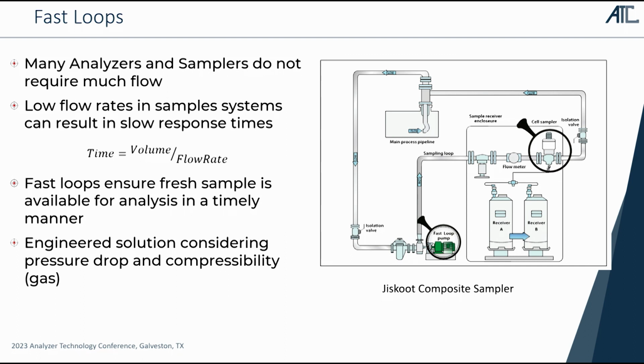Fast loops will help to ensure that we get a fresh sample over to where we're going to do our measurement, and they often have to be engineered properly. If it's liquids, we often have to worry about pressure drops. If it's gases, we have to worry about compressibility. And so there's a lot of factors that can come into play when we're trying to figure out how we are going to design a fast loop for, say, a sampler.